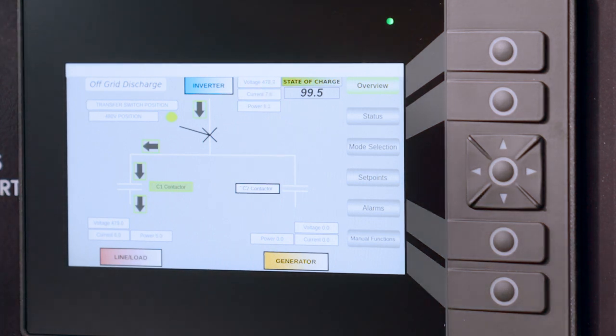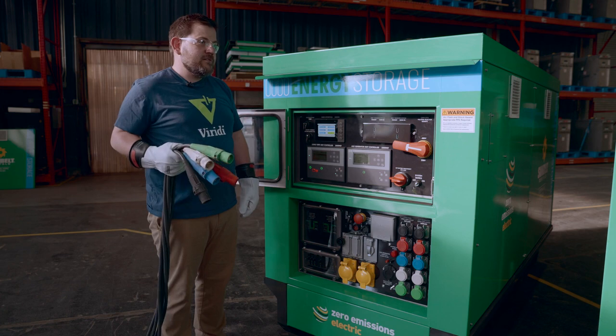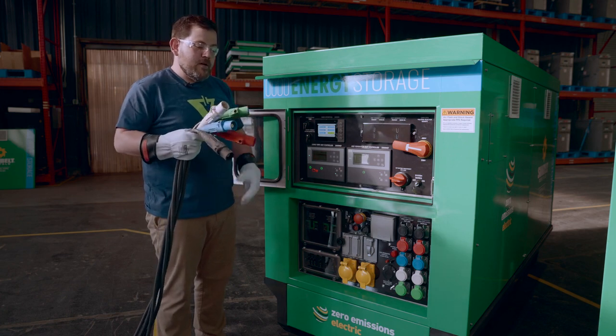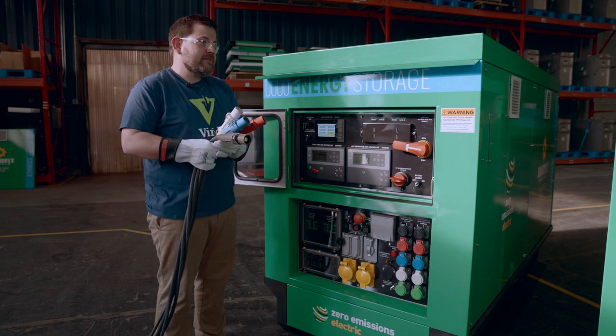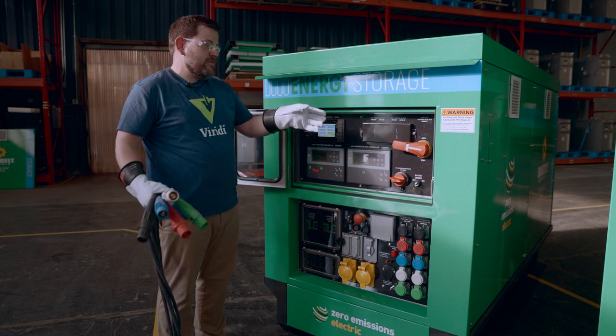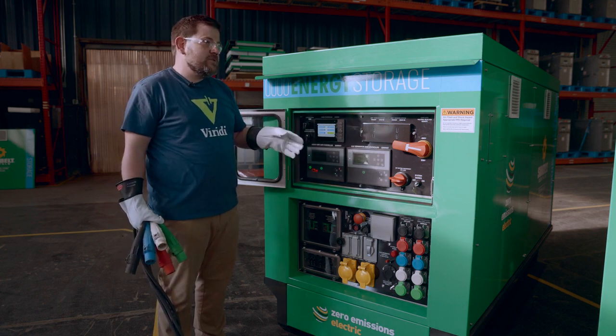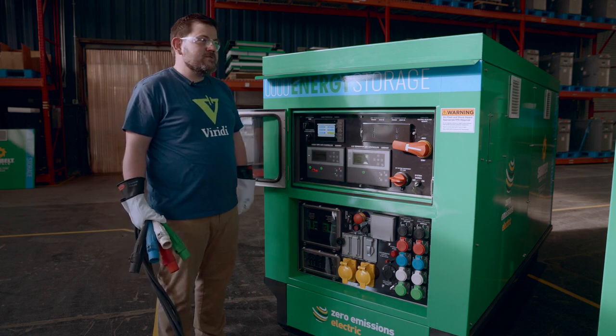Next, we're going to go through a standard on-grid charge to recharge the unit. I'm going to hook up our cam locks to the load grid side from our utility, verify and put our transfer switch in the 480 volt position, and select the on-grid charging mode from our user interface panel.